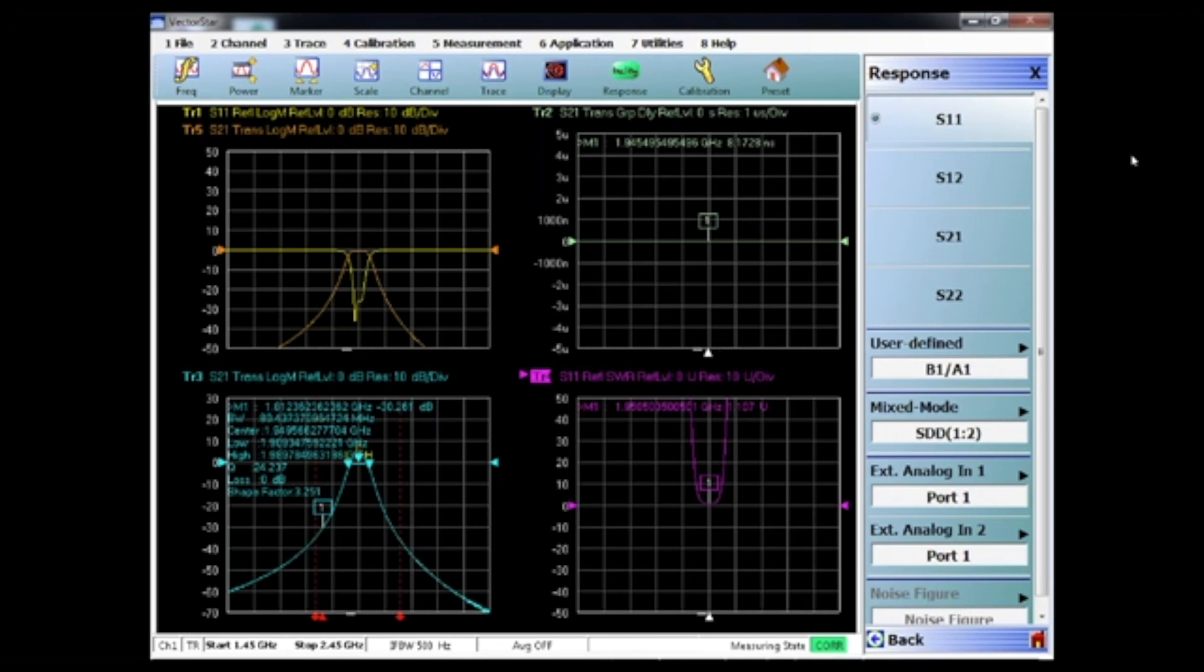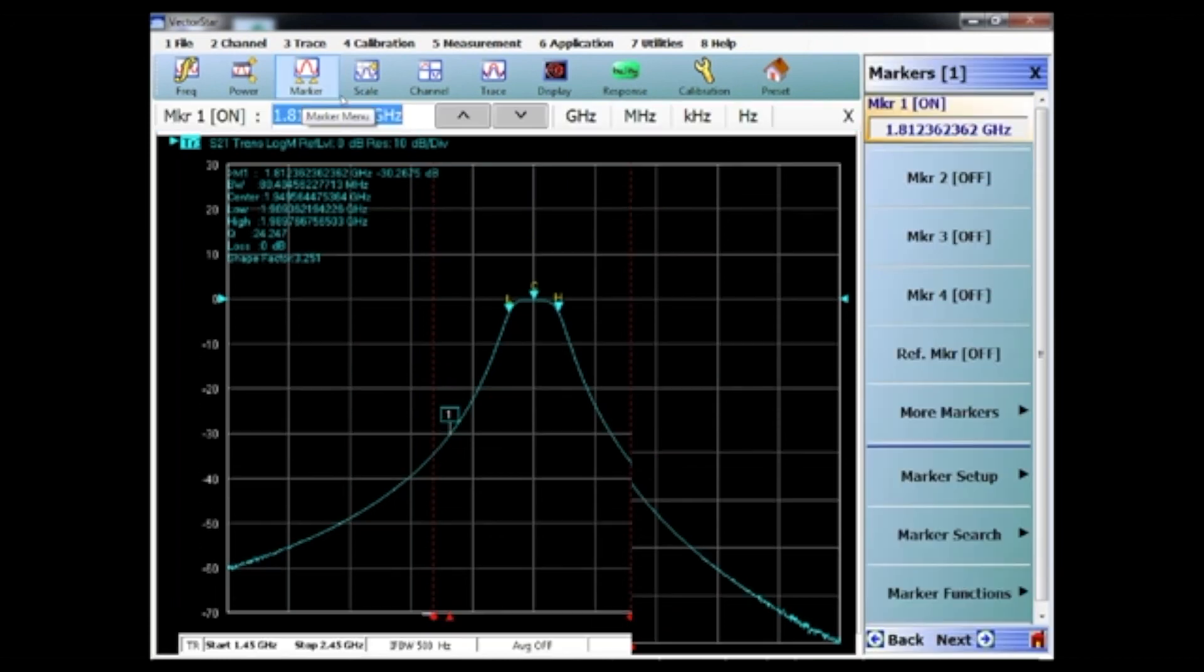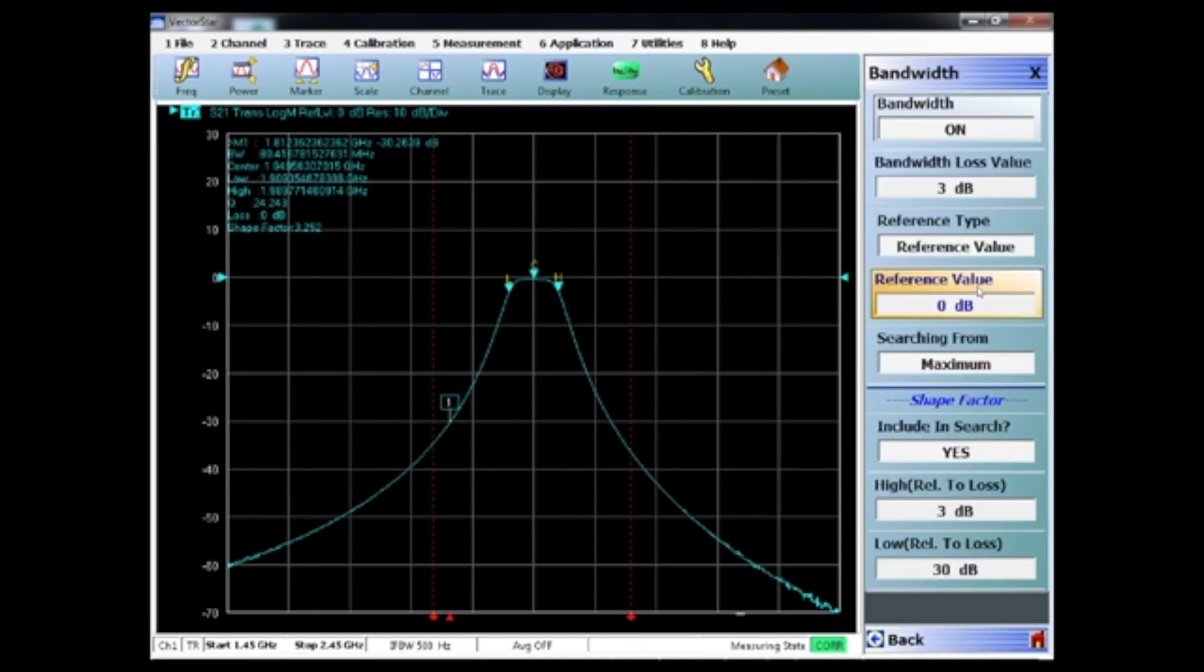So we'll look at the S21, and what you'll notice is that under markers and marker search function, go to advanced, and I'm going to make bandwidth measurements. I have that turned on, and what this is giving me is my Q factor. For this particular filter, it's 24. And then I also have my shape factor, which is 3.251 to 1. So those are all in the benchtop models.